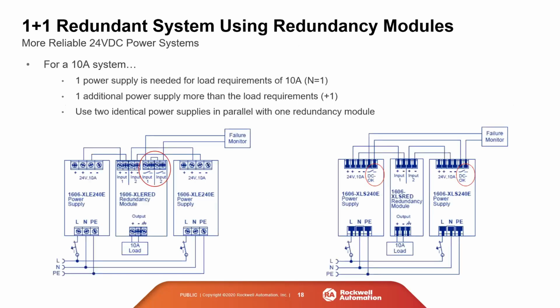So, a 1+1 redundant system using redundancy modules. In this example, we're looking at a 10 amp system. 1 extra power supply must be installed in order to deliver the required current in case 1 power supply in the system fails. In the system on the left, you see we have 2 10 amp power supplies. Our entire system could run on one of these, but the second delivers the required current if the other does fail. So that's our 1+1.